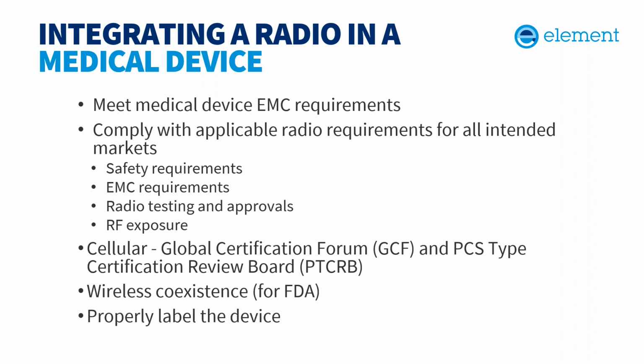Also be aware that the Radio Equipment Directive has safety requirements that refer back to the Low Voltage Directive, meaning tests like dielectric strength and leakage current need to be addressed. Those should already be taken care of by any testing you've done to IEC 60601-1. You might be aware that to meet the Radio Equipment Directive, that needs to be done. You also need to look at RF exposure, which we'll talk about in a couple of slides.